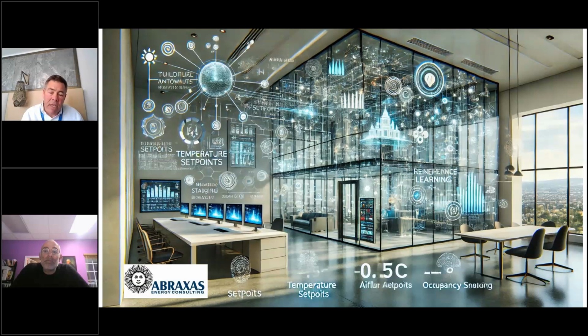We're finding that our reset schedules are a lot finer. In the chilled water plant, for example, we have algorithms constantly assessing the total demand in the building, and we're constantly resetting the chilled water set points. As we reset that, we trend and track all the conditions in the building to see if those resets are impacting energy in the direction we want. If it's not going in that direction, we stop resetting. So all of these autonomous loops are being built, and it's really an exciting time.